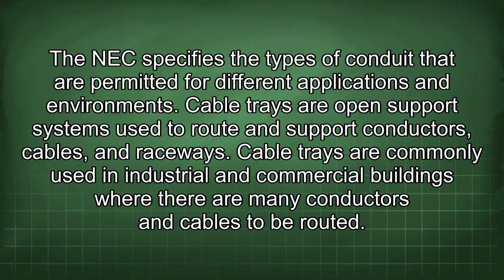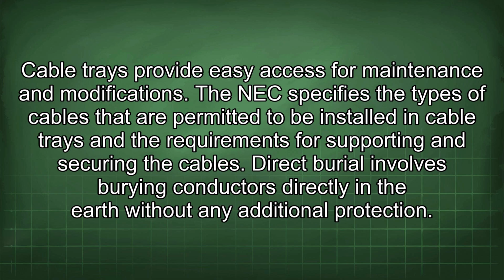Cable trays are open support systems used to route and support conductors, cables, and raceways. Cable trays are commonly used in industrial and commercial buildings where there are many conductors and cables to be routed. Cable trays provide easy access for maintenance and modifications. The NEC specifies the types of cables that are permitted to be installed in cable trays and the requirements for supporting and securing the cables.